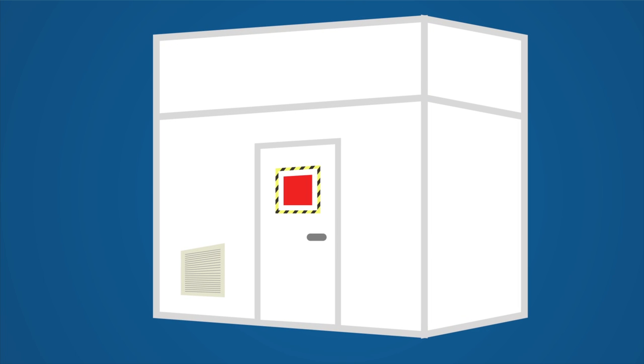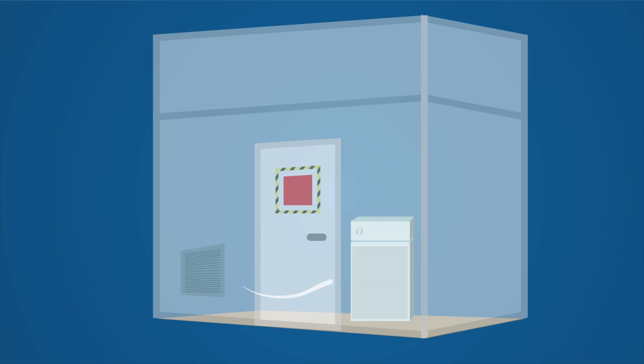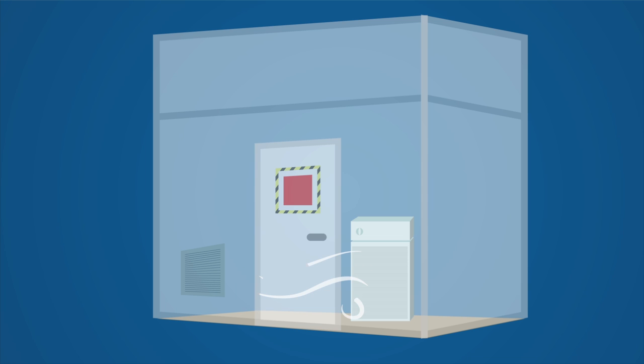One of the fastest ways to accommodate more patients with airborne infections is to create a temporary anti-room out of modular, reusable containment walls, and connect a portable high-efficiency particulate air, or HEPA machine, to one of the walls of the anti-room. The HEPA machine causes the anti-room to become negative pressure by pulling air from the patient room and corridor into the anti-room, preventing the infection from spreading through the hospital.